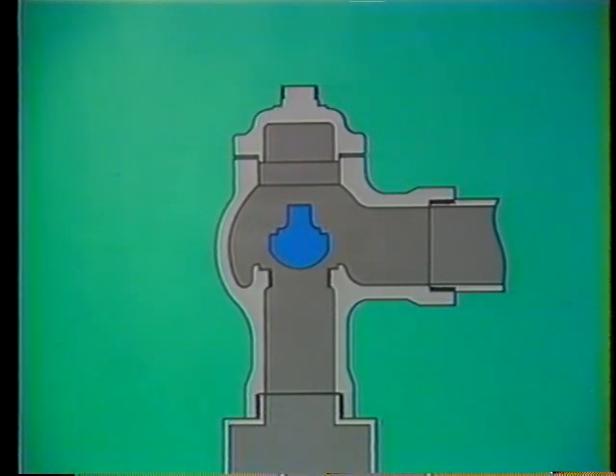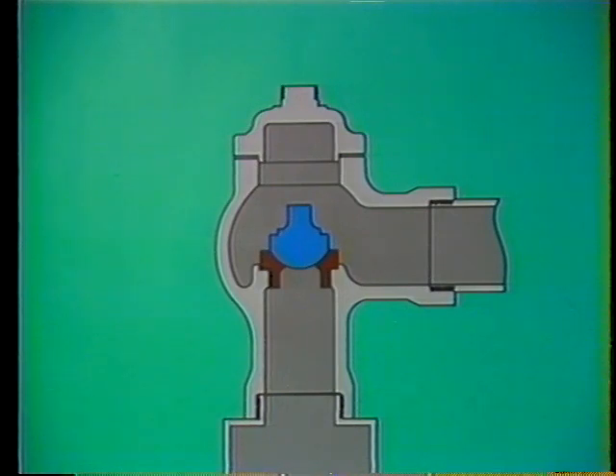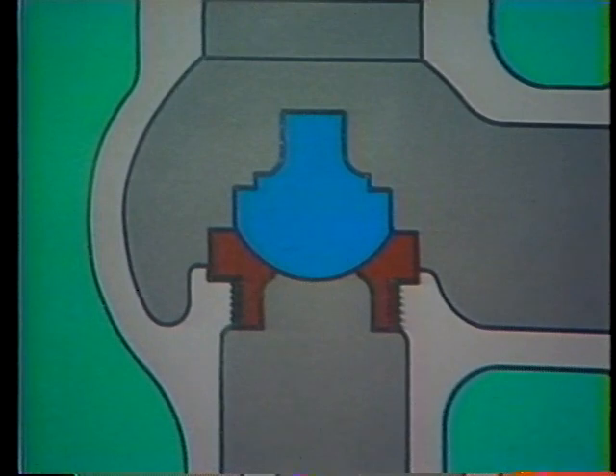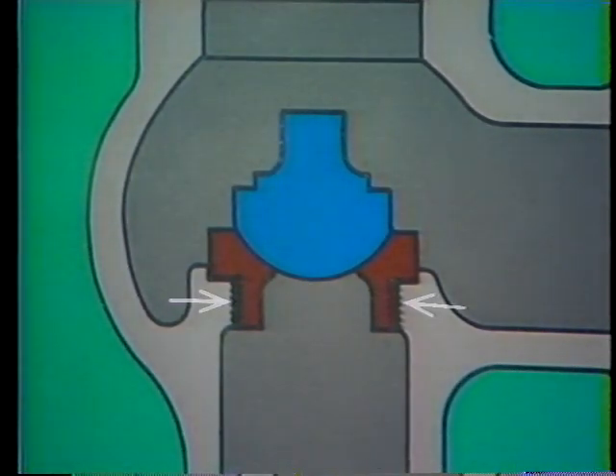In many high-pressure applications, the inlet might be flanged or even welded directly to the system the valve is protecting. Liquid is prevented from leaking around the disc by firm, even contact between the disc and a seat. In some valves, the seat is a permanent part of the valve body. In others, a threaded seat bushing is used. Because it's threaded, a seat bushing can be replaced if necessary.